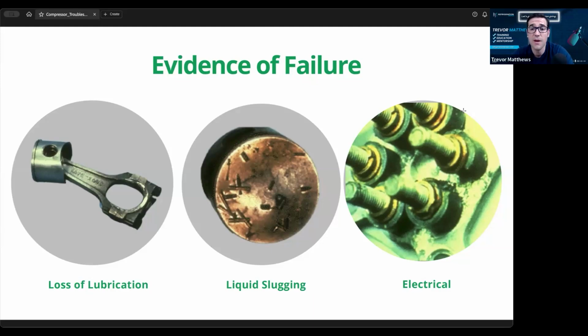Yes. I'm sure you've seen this before. Pull the insulators off and then check it. That's how you verify 100% if it's the compressor, or maybe it's that insulator you were talking about, like on those Carriers. Insulators have carbon in them, and I always put on the new insulators that come with a compressor. Don't reuse the old insulator. Always use a new one, because, like I said, they'll short out and run a lightning trail almost. When you turn it on, it'll sound like an explosion. So I don't want that to happen.